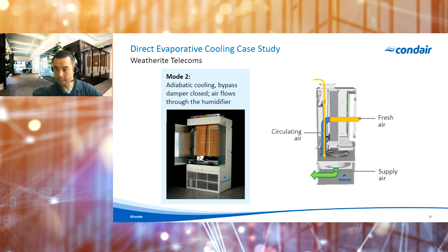So if we look at the Weatherite unit, you can see the media in here. This is cassetted media. Media can come in either cassettes or just freestanding. The cassettes tend to make installation and removal a little bit easier, though there is some cost associated with that. So in this unit, you would disconnect the recirculation hose, you would undo some bolts, you pull the cassettes out, and you put new ones in. It's pretty straightforward.